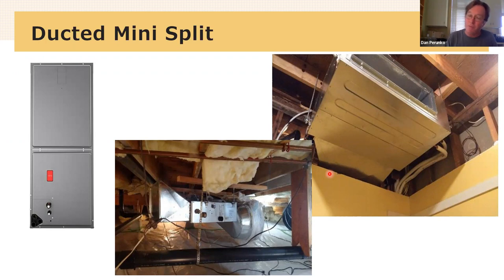If you were to do a load calculation for a home, it will tell you, I need 26,000 BTUs per hour to air condition this house at peak conditions. It'll also tell you that I need 29,000 BTUs per hour to heat this house at peak conditions. And so those are just over 2 tons, right? 24,000 BTUs per hour is 2 tons, 26,000 BTUs per hour is like 2.1 tons. And so that's how we talk about the equipment. When you're actually making those decisions, doing a load calculation and picking equipment, you're going to look into what's called expanded data, and it'll all be in BTUs per hour, and I'll show you that later. So tons is sort of a general way to talk about things. Then there's real specific design information we also have to look at.